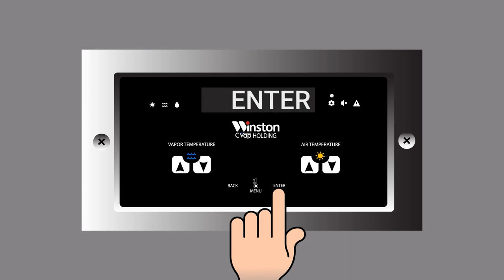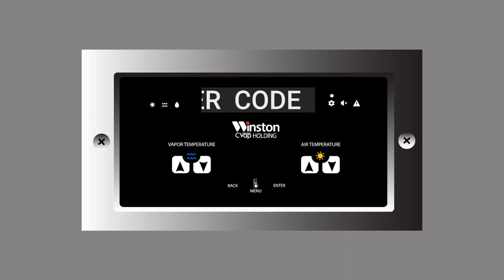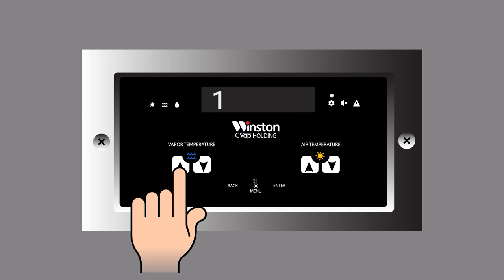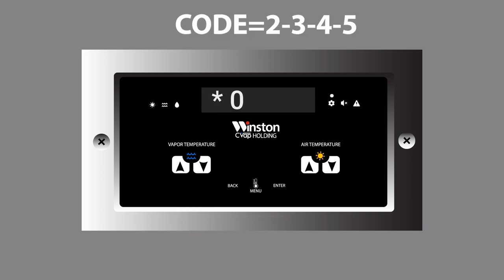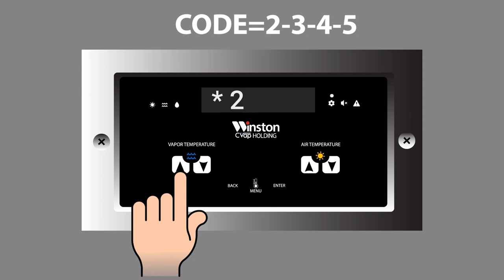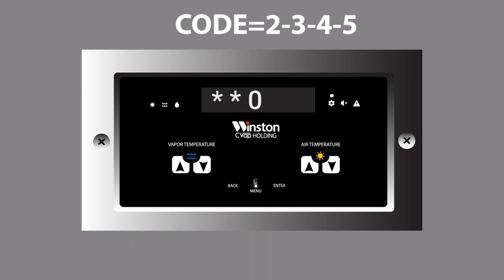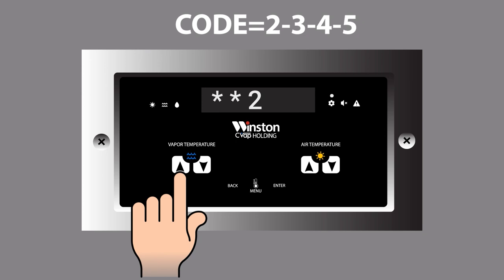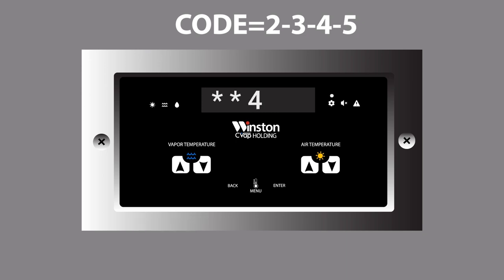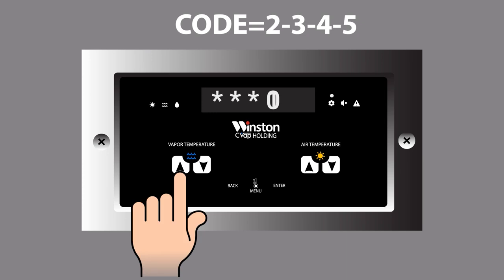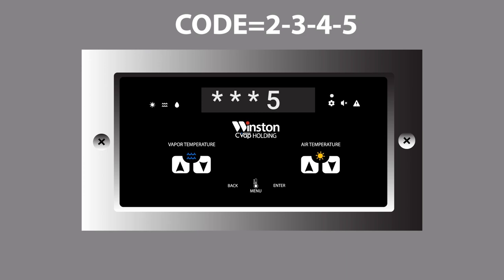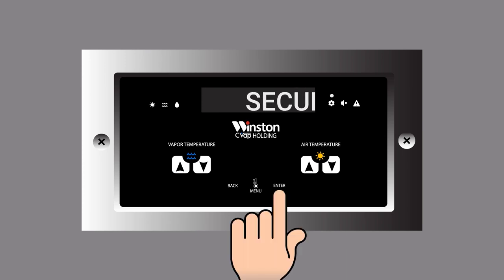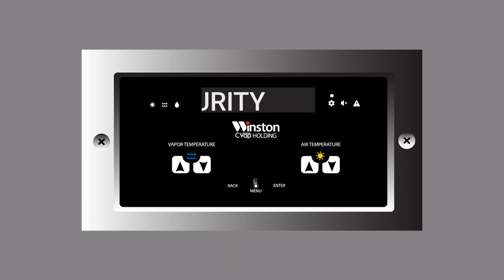Select Enter. Enter code will be displayed. Using the vapor temperature up and down buttons, enter the code. 2, press Enter. 3, press Enter. 4, press Enter. 5, press Enter. The security lock is now enabled, and security will be displayed. The code must be entered again to disable the lock.